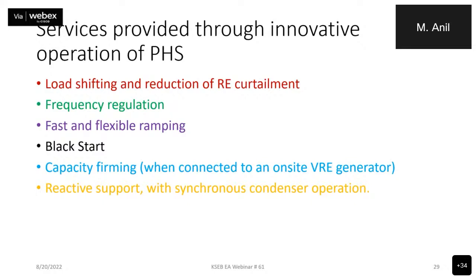That is, during high RE generation, the pumping can be undertaken from the lower reservoir to the upper reservoir. So that way RE curtailment can be avoided. Frequency regulation, that is during peak hours, the generator can be made to function and frequency can be maintained. Fast and flexible ramping, black start operation, capacity firming when connected to an on-site VRE generator, and reactive support with synchronous condenser operation. The pump at the lower reservoir level can be operated as a synchronous condenser to provide the necessary reactive support.